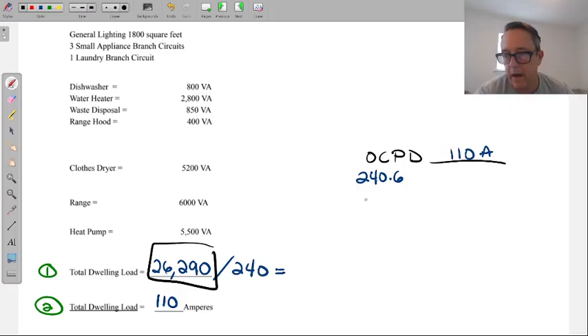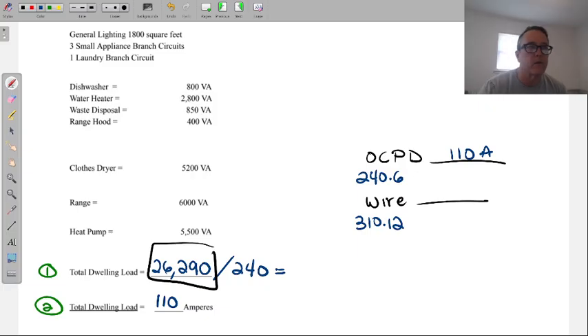Now for the conductor or wire, to make it easy, we don't go to 310.16. Everybody does this the first time with these questions — you go to 310.16, where we always size wires, take the 110, use the 75 or 60 degree column, and feel good remembering all that, but we forgot the main thing: it's the wrong article to begin with. The right one is 310.12. It's a table — and like all tables, it has an article that goes with it — but ultimately we're looking for the table, which is on a page I'll mention in a second.